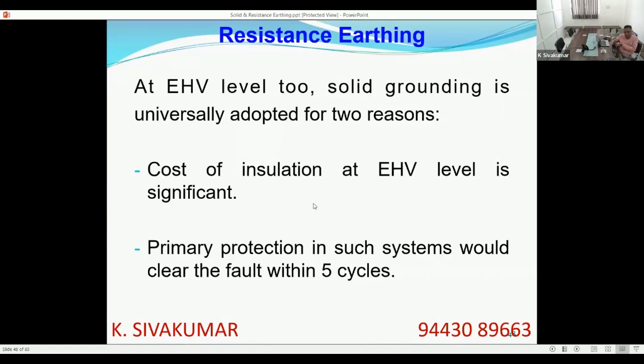Even if you go higher, it is still higher. Say 110 kV or 110 by root 3, or 132 by root 3, or 220 by root 3, 400. So as you go higher and higher, there is a big advantage in cost savings in insulation costs if you go for solid grounding. So definitely, this is a very significant point in going for solid grounding in EHV systems.